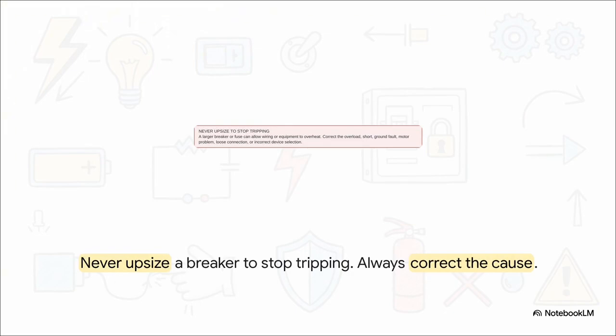I know it can be incredibly tempting to just throw in a bigger fuse or upsize the breaker so it stops nuisance tripping all the time. But if you do that, you've just completely removed your safety net. A larger breaker could allow your wiring to carry way more current than it can handle, causing it to overheat and potentially catch fire. A blown fuse or a tripped breaker is a symptom, it's not the root cause. You absolutely have to correct the overload, the short or the failing motor before you restore power.